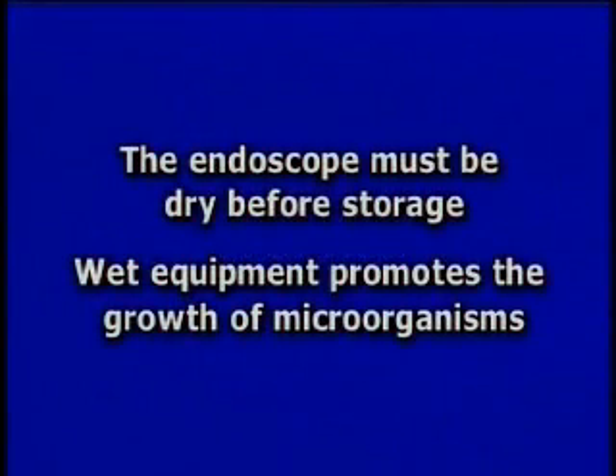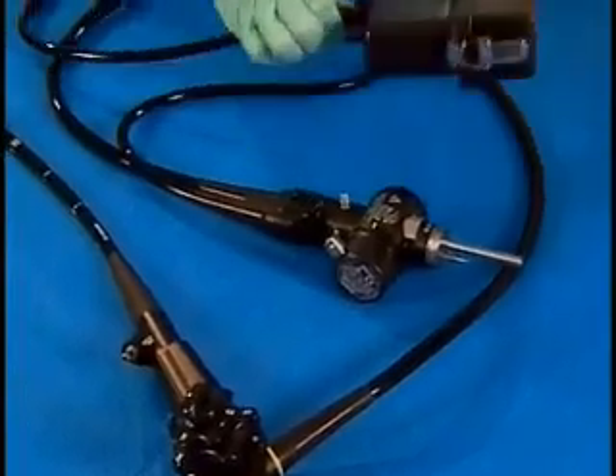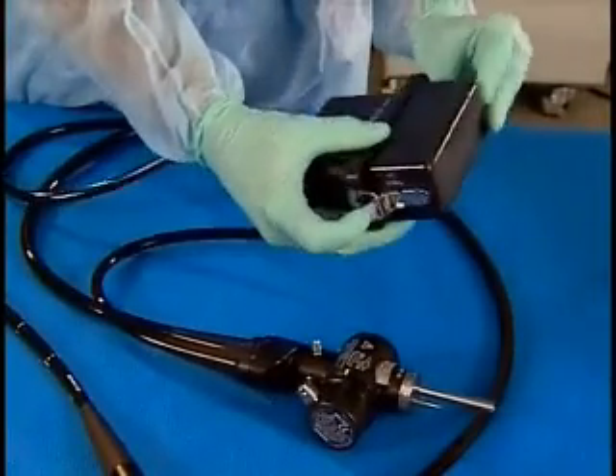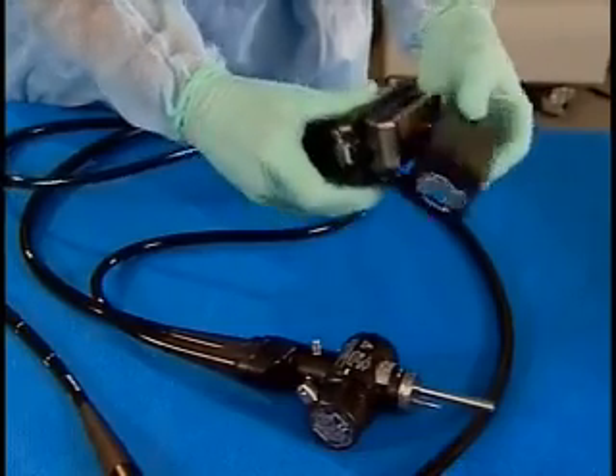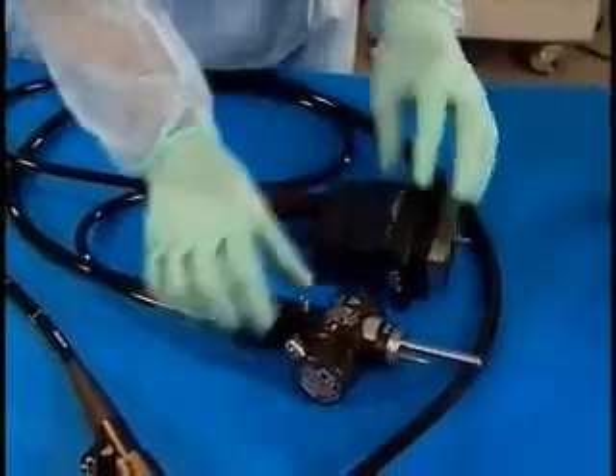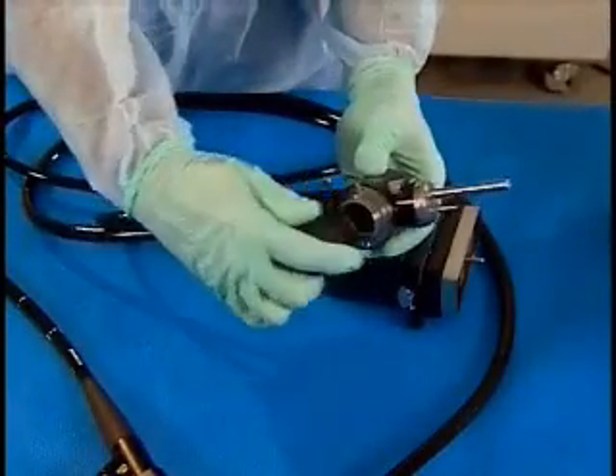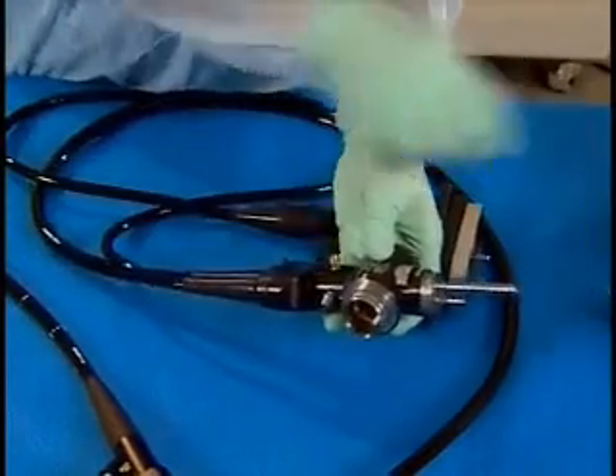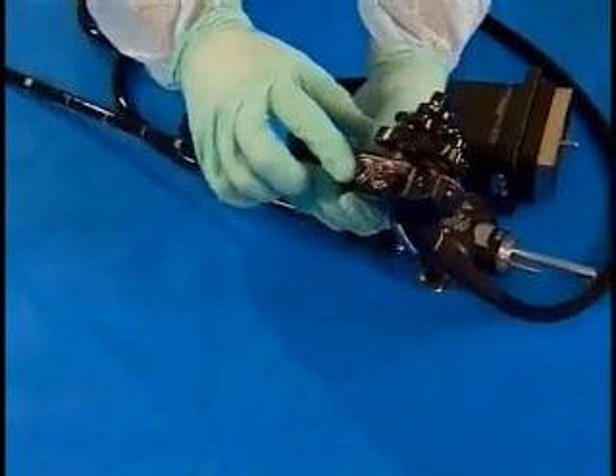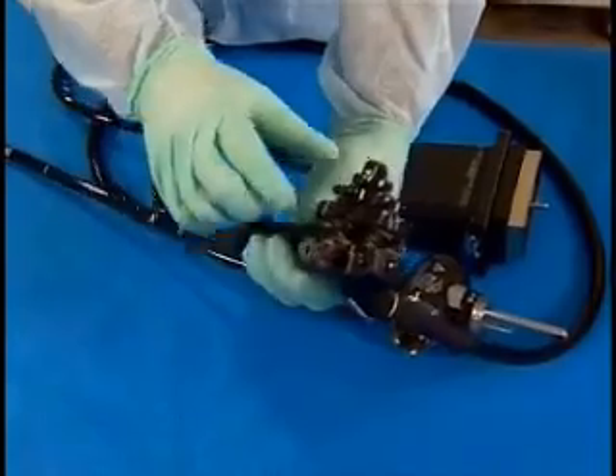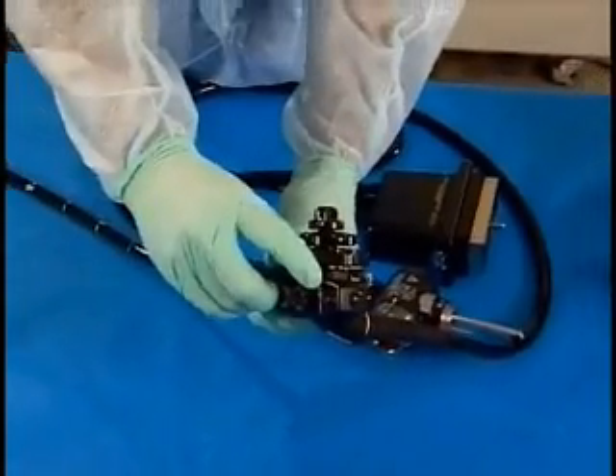If you plan to store the endoscope, ensure that all channels of the endoscope are dry. Wet channels promote the growth of microorganisms and present an infection control risk. Prior to storage, remove the water-resistant caps from the endoscope. And make sure that all valves have been removed. Also check that the angulation locks are in their free position.